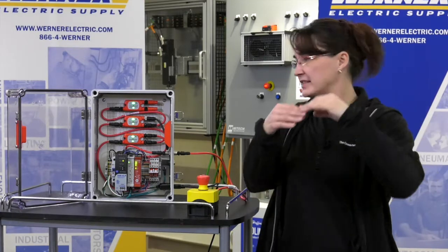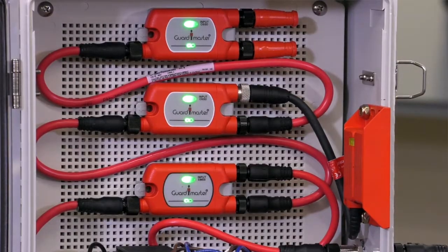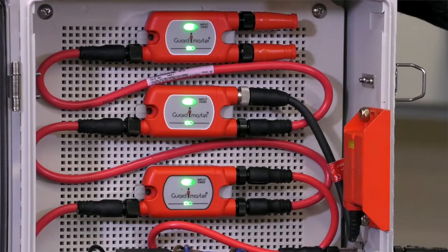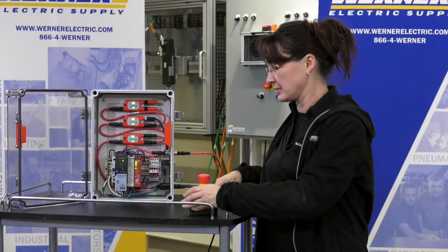And then from the tap, which is the device connection, you get an additional 10 meters. So for instance, say this one right here has three taps on it — between each tap you can do 30 meters, and from the tap to the device is 10 meters.